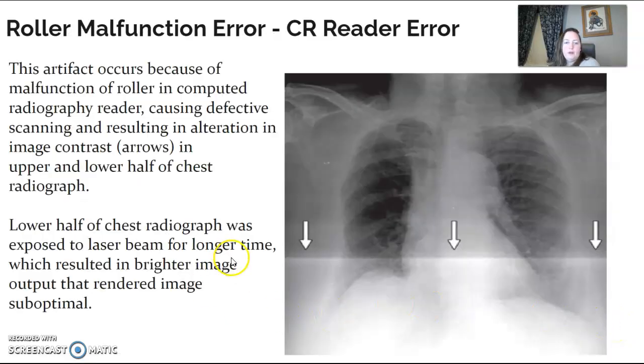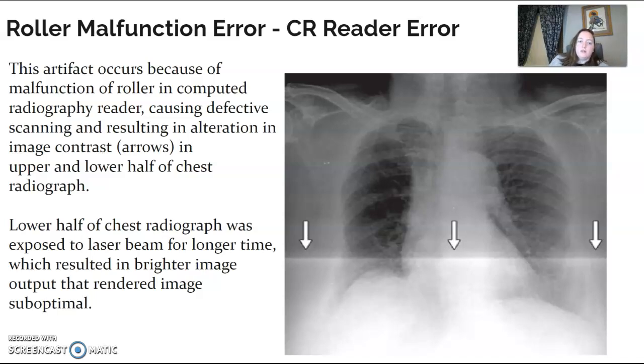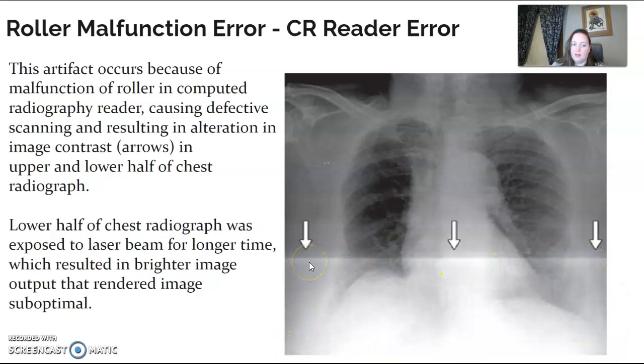Roller malfunction error. You can see this clear line — something happened within the rollers. With the CR plate, it takes the imaging plate through a set of rollers inside the CR processor. If there's a malfunction when it's scanning, it can be under the beam for a longer amount of time than it's supposed to be. This whole section ended up being a lot brighter, and the artifact was right through the area of anatomy, so it would most likely have to be repeated.